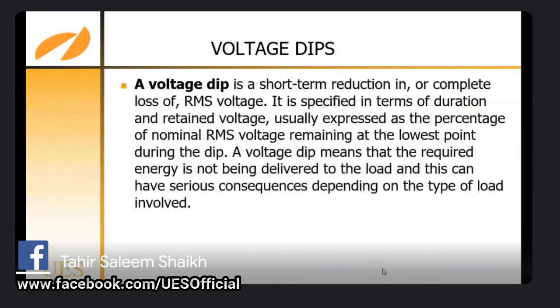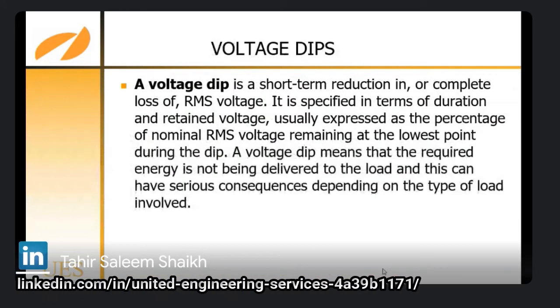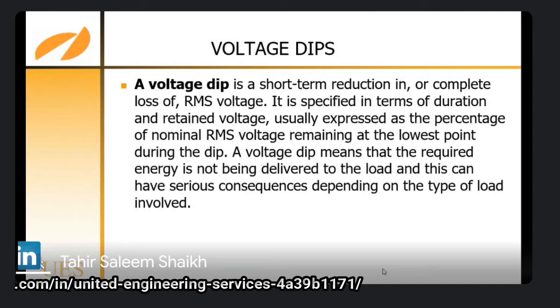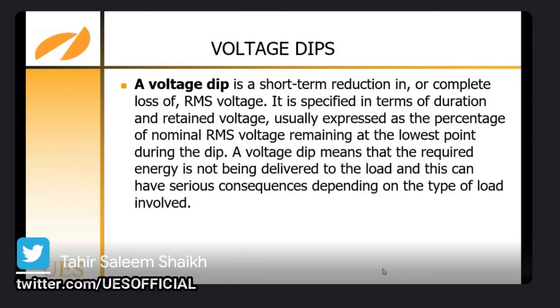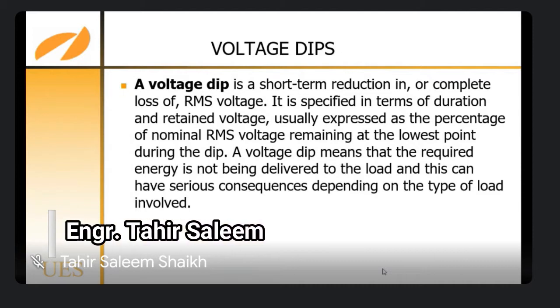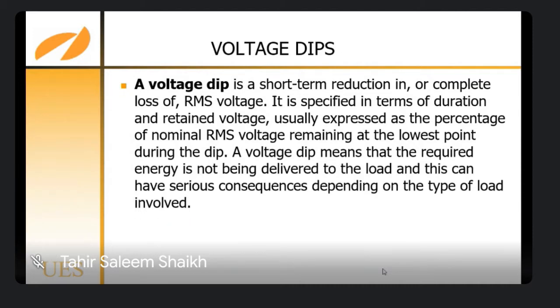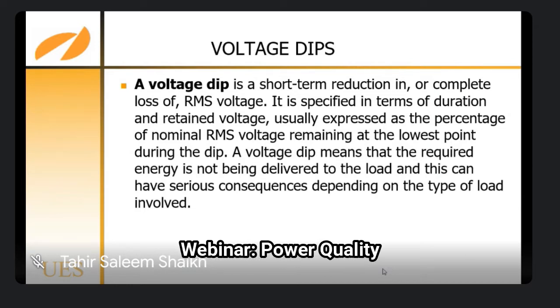Now, coming to voltage dips: a voltage dip is a short reduction or a complete loss of RMS voltage. It is specified in terms of duration and retained voltage, usually expressed as a percentage of the nominal RMS voltage remaining at the lowest point during the dip. A voltage dip means that the required energy is not being delivered to the load, and this can have serious consequences depending on the type of loads involved.